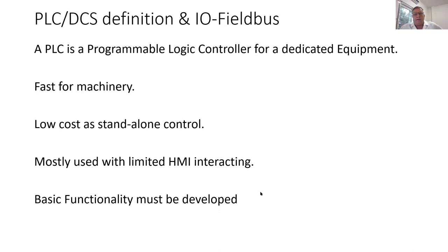Yeah. So in principle, that is a basic function. It's a digital input, and we have others like analog inputs, analog outputs, PID controller, and these function blocks are normally used in a DCS. So that makes it very easy to put in an I/O channel, do some basic configurations, and get signals for your alarm or whatever you need. So that is what I mean with basic functionality. So you have to go and build up your own function blocks, which you can use later for your process signals and the sensors and actuators.